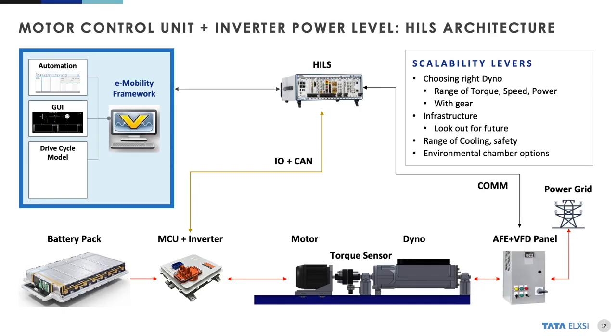The motor, whose shaft is extended through a torque sensor, is connected to a dynamometer or dyno. The dyno is controlled by an AFE VFD panel, where AFE stands for active front end and VFD stands for variable frequency drive. This panel is connected to the power grid.